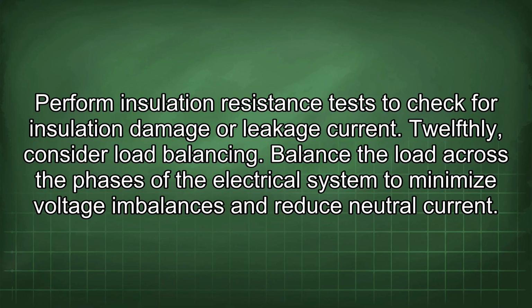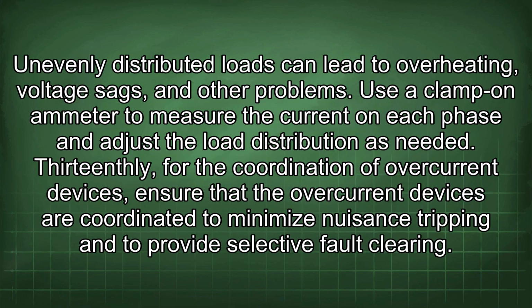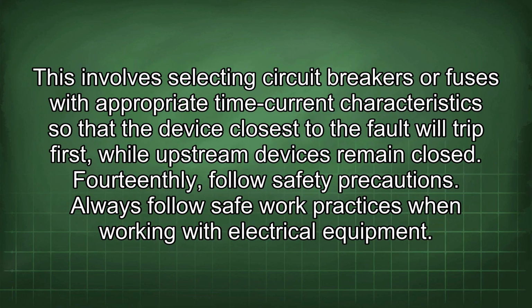Twelfthly, consider load balancing. Balance the load across the phases of the electrical system to minimize voltage imbalances and reduce neutral current. Unevenly distributed loads can lead to overheating, voltage sags, and other problems. Use a clamp-on ammeter to measure the current on each phase and adjust the load distribution as needed. Thirteenthly, for the coordination of overcurrent devices, ensure that the overcurrent devices are coordinated to minimize nuisance tripping and to provide selective fault clearing. This involves selecting circuit breakers or fuses with appropriate time-current characteristics so that the device closest to the fault will trip first, while upstream devices remain closed.